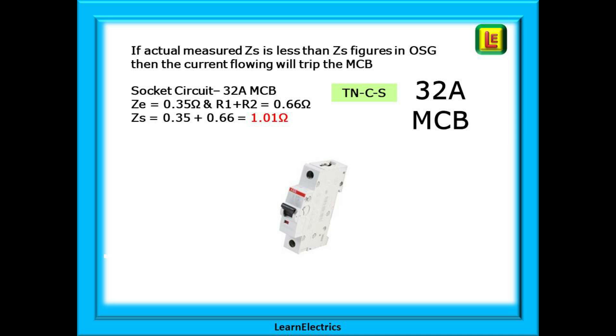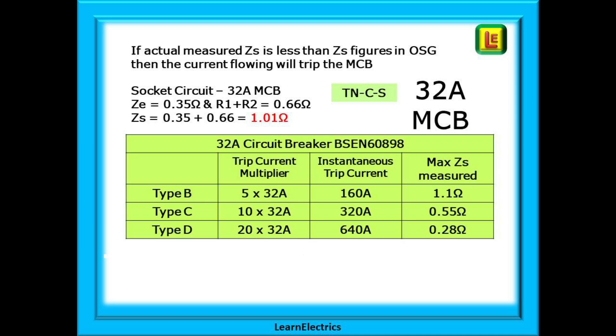Go on now and consider a 32 amp socket circuit. It is still a TNCS system and the ZE remains at the maximum of 0.35 ohms. The R1 plus R2 this time is 0.66 ohms. So ZS must be 0.35 plus 0.66 which is 1.01 ohms. Looking at the table for 32 amp breakers, we note that with an actual ZS of 1.01 ohms, the circuit is just below the permitted maximum of 1.1 ohms for a type B. But the types C and D are both outside the specified range. Making comparisons like this will help you to design and install circuits safely and correctly and comply with the wiring regulations and the building regulations.